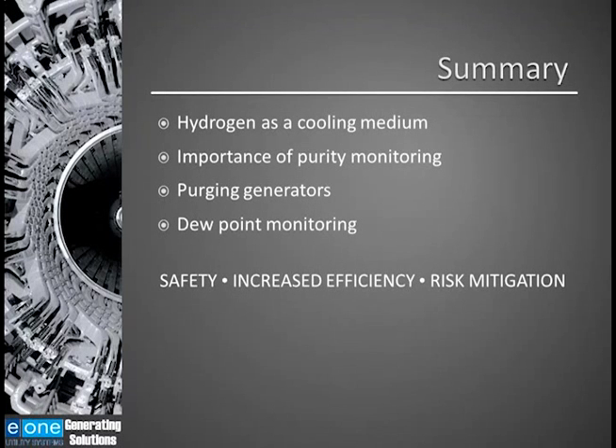In closing, we know that hydrogen is a very effective cooling gas. By using hydrogen as a cooling medium, you can get more megawatts without increasing the physical size of the generator. Again, more megawatts per pound of iron. Recent catastrophic events have reinforced the critical importance of safety and risk mitigation strategies in power plants worldwide.